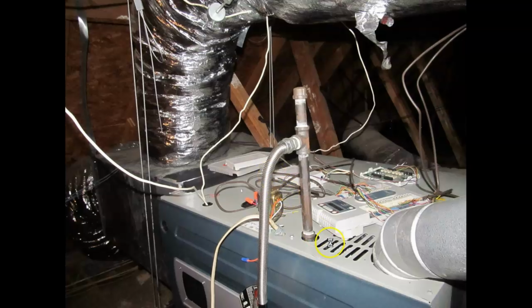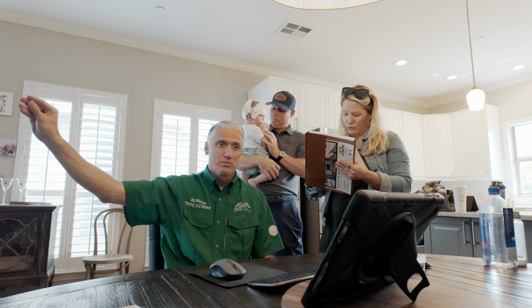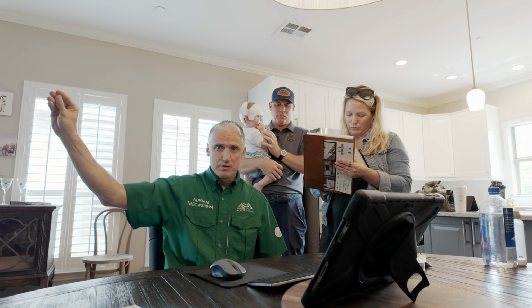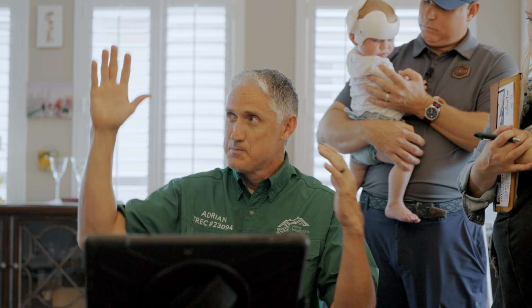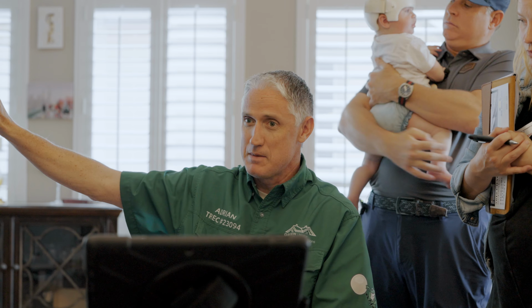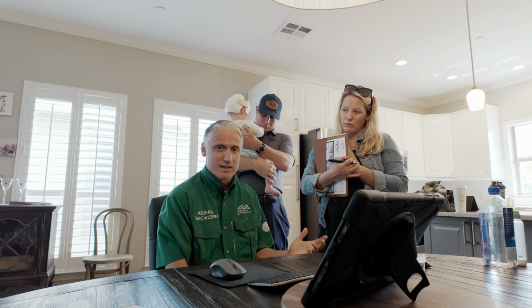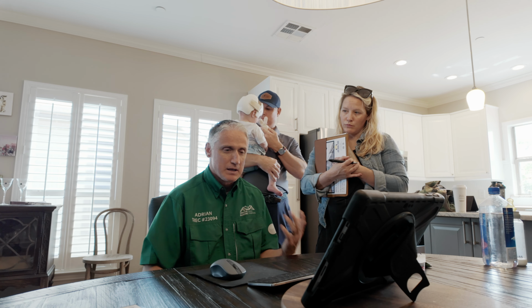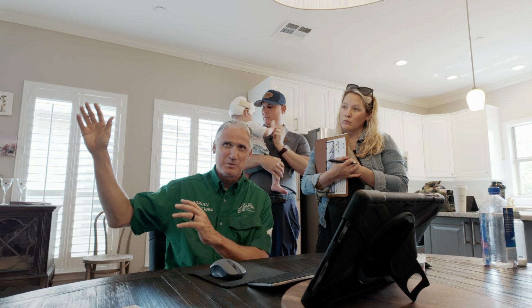I don't know if you can see all this stuff along the top here, there's lots of wires. This is part of the zoning system for the two thermostats, and something is not wired right, because when I adjust the thermostat in the bedroom, it produces cold air downstairs. They had the thermostat off downstairs. Since there are two thermostats, it would be nice to be able to control that. That's why it's so cold downstairs - the ductwork has been compressed, making the master bedroom really hot, and they've been running the air probably continuously. That's why it was like 70 or 65 degrees downstairs when I came in, because it's just constantly running since it can't get the upstairs cool enough.